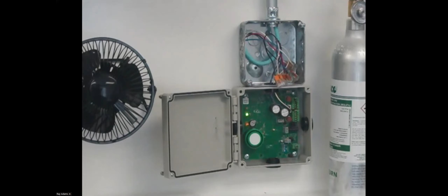Now, as I talked about before regarding the sequence of operations of the detectors, both our standalone and our control panel have built-in controls that are designed to control the ventilation equipment within the facility. We do offer a building management system transmitter that is just an individual sensor that simply sends a gas value back to a building management system. So there are no controls and no fan functions built into it. You're simply sending the signal back to a building management system, where the building management system would be able to turn on your ventilation equipment and control whatever else might be in the facility.